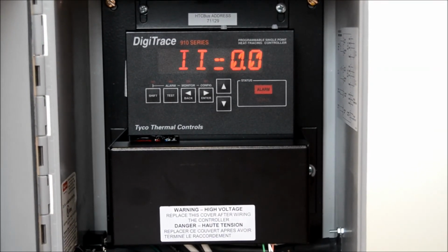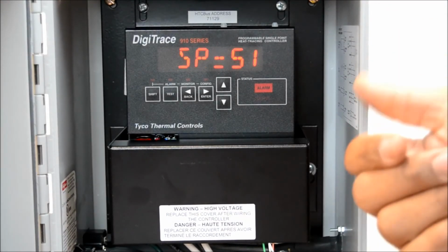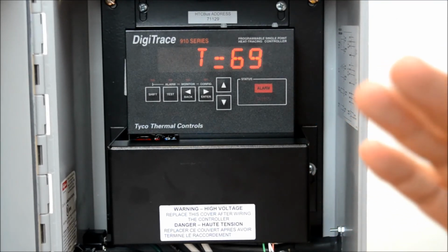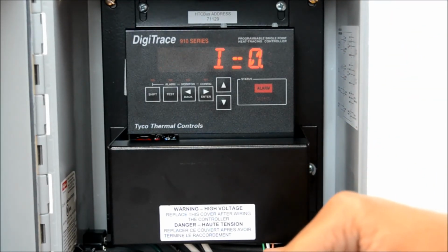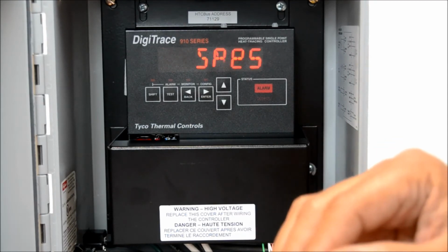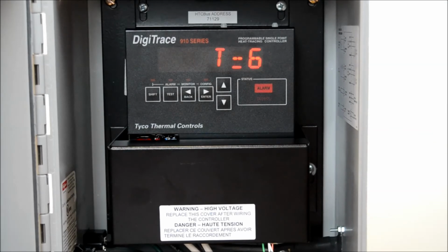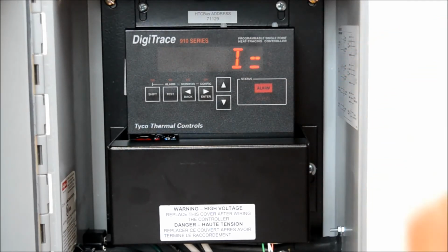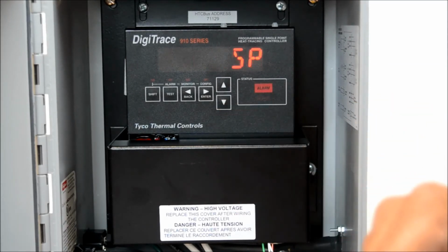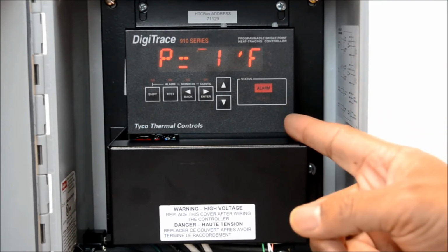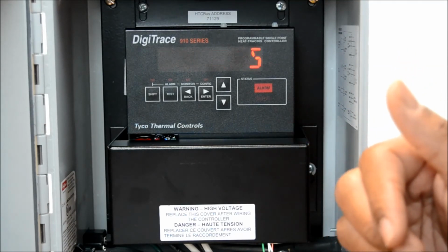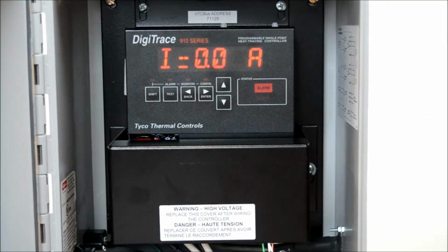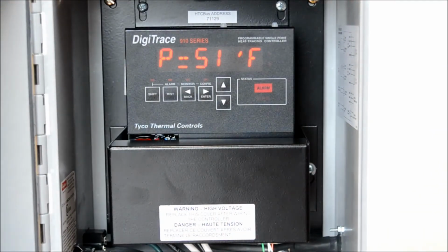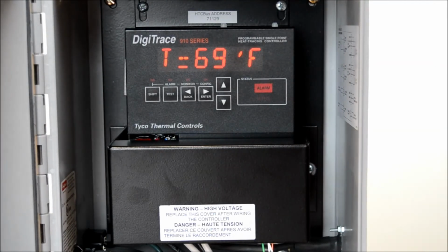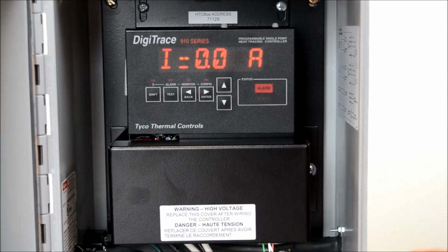Now for troubleshooting, if it says a low temperature alarm, or no temperature reading, you want to make sure that these wires for the RTD are connected. If it gives you a low heat trace alarm or low power alarm, what you want to do is make sure you check the heat trace circuit to make sure that the heat trace is working correctly. If you get a GFI or a ground fault alarm, you're going to have to check the heat trace from the power connection box. And essentially, that's how you clear an alarm.